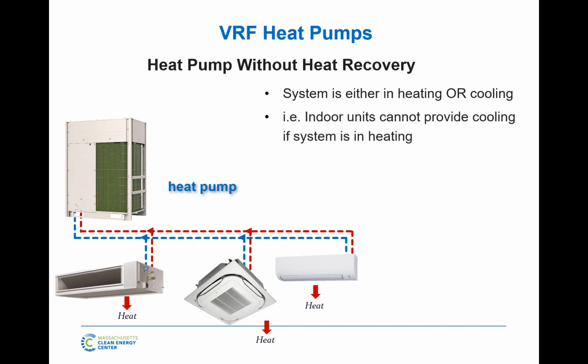Now, a couple advantages of this system versus a two-pipe chiller fan coil system. One of them is I might have multiple of these systems in a building. So I might have one system serving all my north classrooms or all my north suites in a multi-res building, and one system serving the south. So all the units on the north can be tied to one machine that's going to be in heating mode today and in the afternoon, for example. Whereas on the south, I can have a unit that is facing the sun. They're all getting warm, so I can have that system in cooling mode. But within the system, all the south units are all in the same mode. That's one advantage. So now I've zoned my building a little bit.